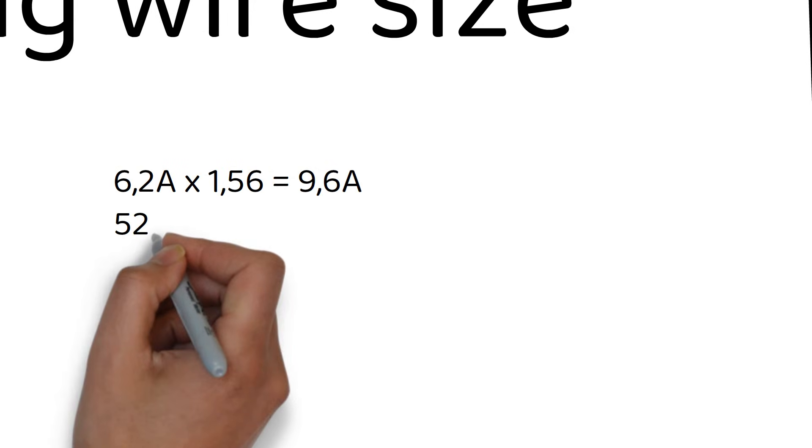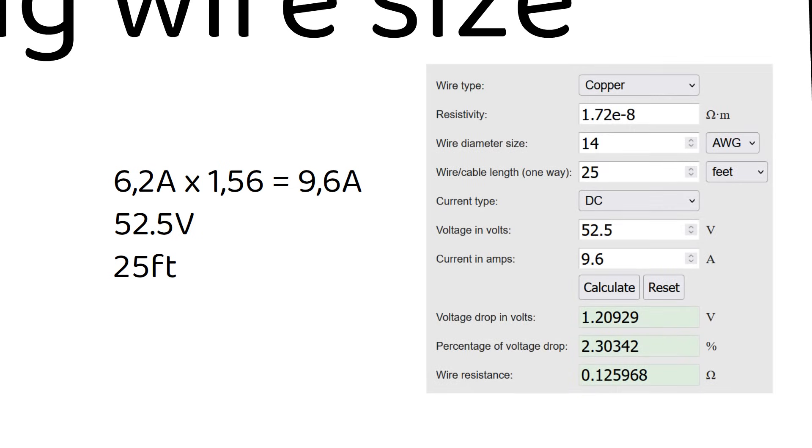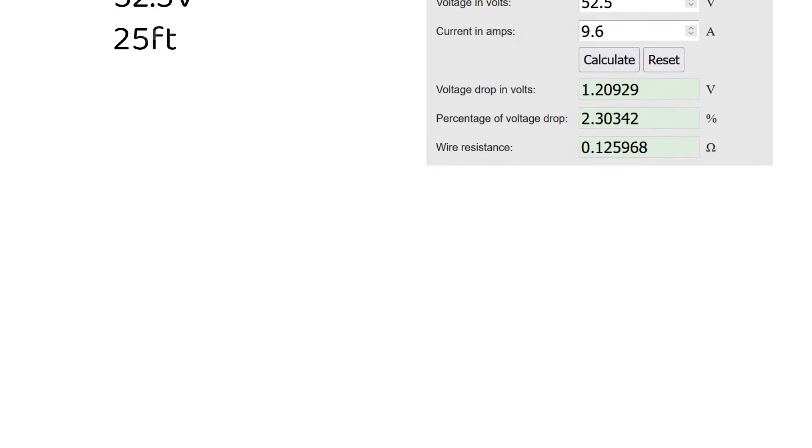The wire from the solar panels to the charge controller needs to be calculated according to the short circuit current of the solar panel. This is 6.2A times 1.56 equals 9.6A. The combined voltage of the 3 solar panels is 52.5V. If we calculate this for the voltage drop, we can see that a 14 gauge or 2.5mm square wire is good for 25 feet length.